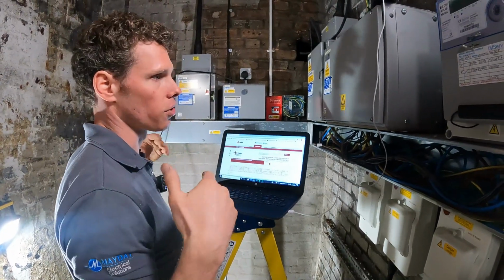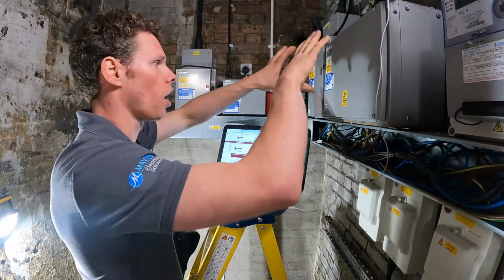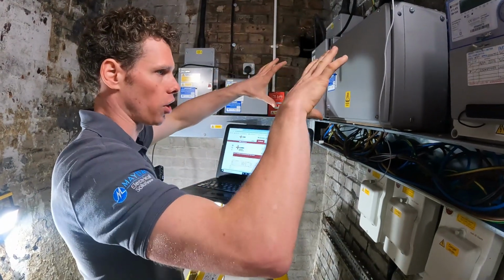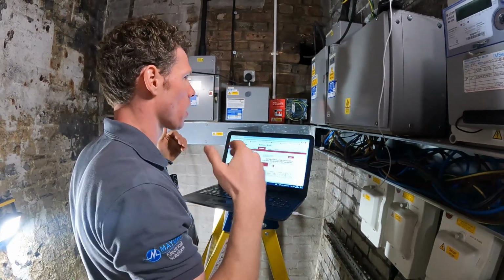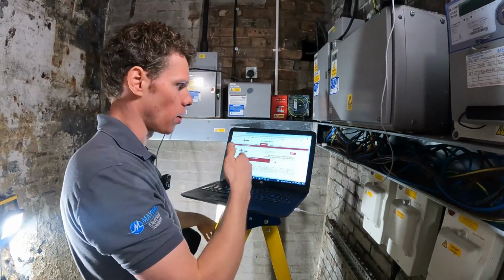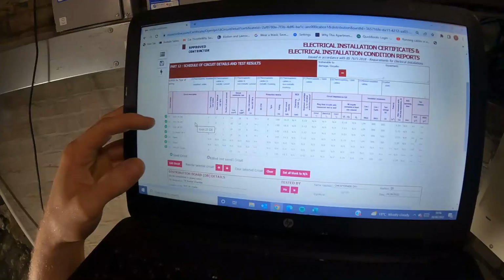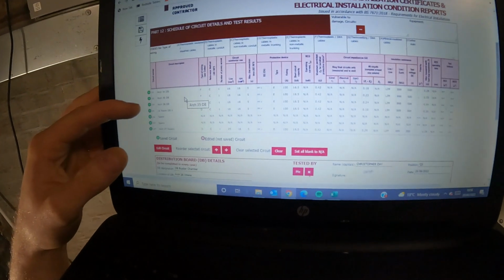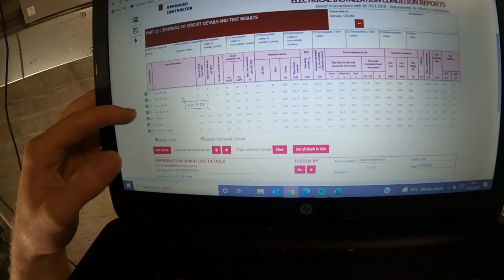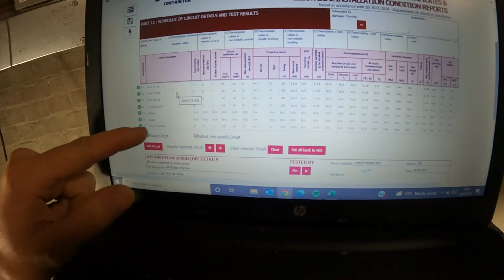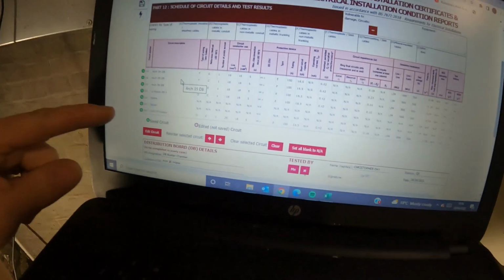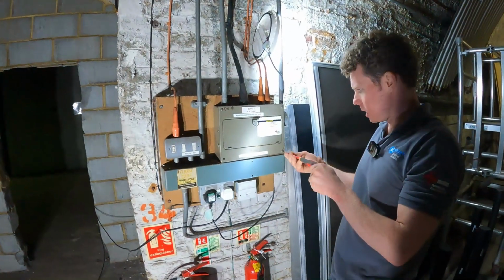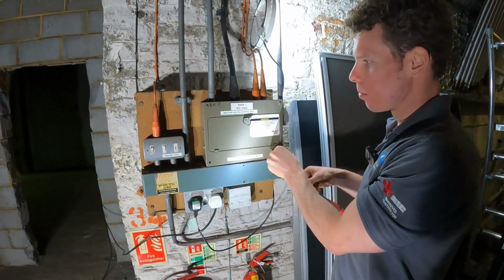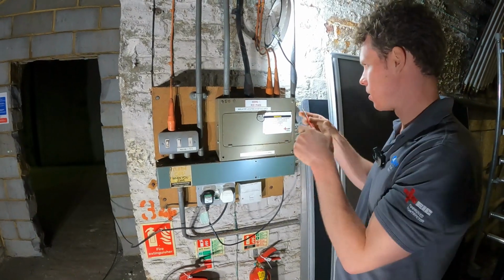I go to the origin of the installation whenever I do a larger job, and I'd start at the busbar chamber, which gets inputted onto the software as if it's a fuse board. Arch 35, 1L2, Arch 33, 36 on 1L3, and then we've got the LV room DB4 there, and a three-phase supply coming off, that's the main isolator switch over there. Right, so one thing to immediately note is there's a missing screw.